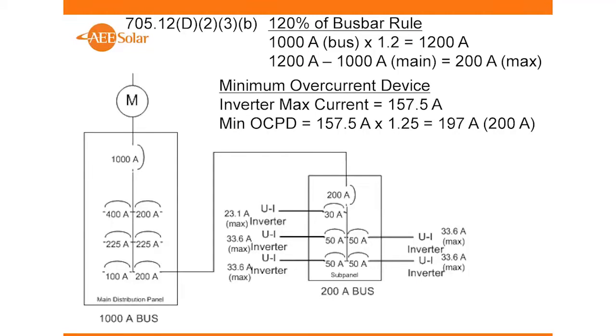Go back to our little sub panel examples. Okay, I could have a much smaller PV system out here, right, and connect it to a 200 amp sub panel. That doesn't make this a 200 amp supply breaker. The code says the connection of the inverter breaker, that connection is used for all upstream calculations, not this guy. And it specifically says that for that very reason, because I might have a 40 amp breaker at this panel over here, and the 120% rule works fine on that, but I'm not going to call it a 200 amp breaker when I get to here. It's still a 40 amp breaker connected into this main panel. Does that make sense? That's the way the code's been written for 4 or 5 code cycles.